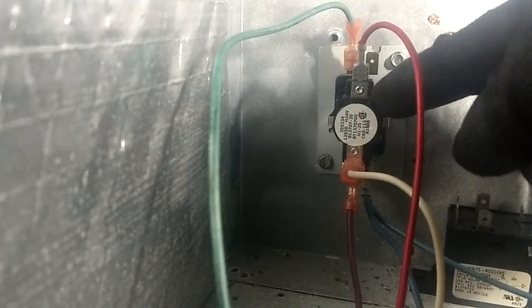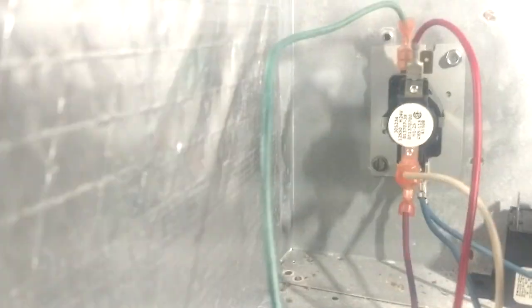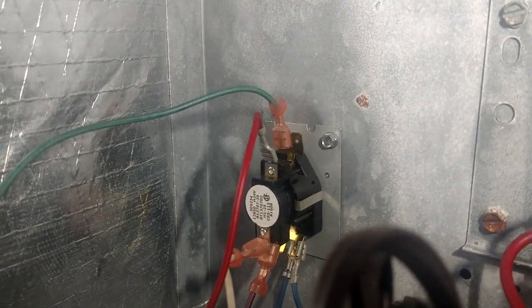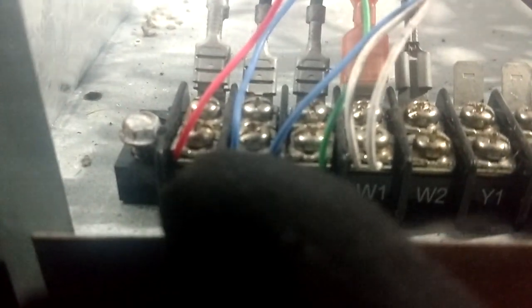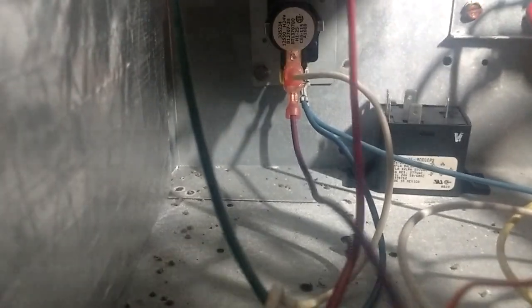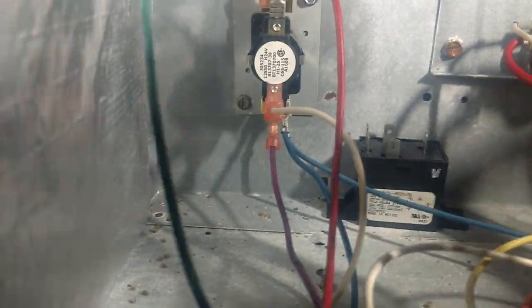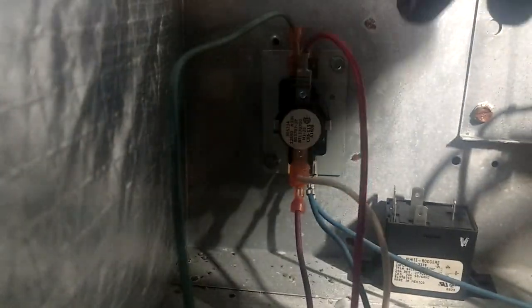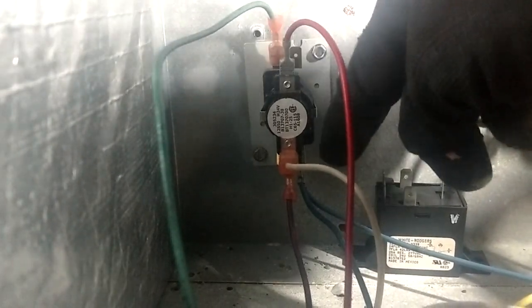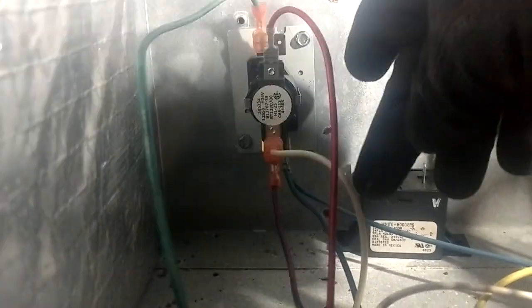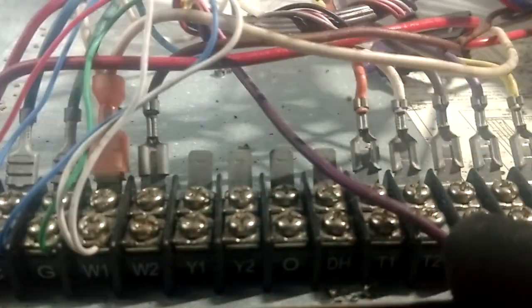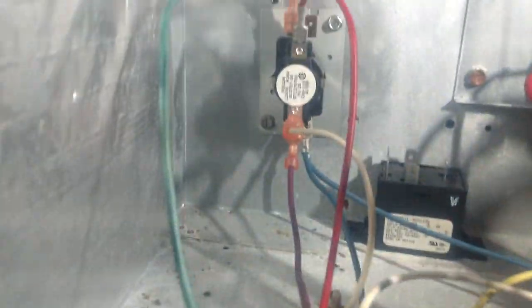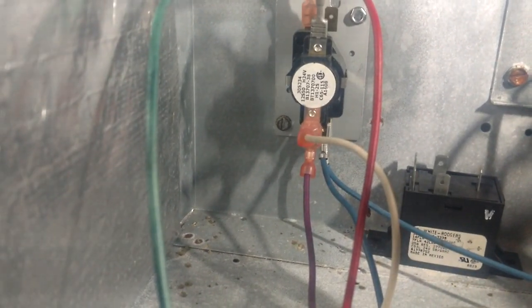Low voltage. So our normally open set of contacts is over here on this side and down to that purple wire. Alright, so the red wire runs back over here to 24 volts. That's constant 24 volt power sitting right there all the time, and it's waiting on the green wire to power the coil of the relay and close that normally open contact and send power from the red wire to the purple wire, which comes over here to the white and turns the blower on. So we need to verify whether that's happening now or not.